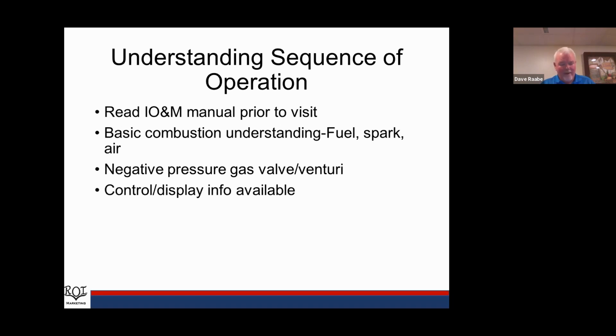So the important thing when we run into trouble on a boiler is understanding the sequence of operation. So we need to know what's supposed to happen and in what order. Having a basic understanding of combustion, we need fuel, spark, and air. But in a condensing boiler, most of the time, our air is provided by a fan attached to our gas valve. The control of the boiler will tell that fan what speed to run at. So, and then we're providing fuel and trying to light a flame at a certain point off of that burner. So these are basically power gas burners inside a boiler. You can think of them that way.